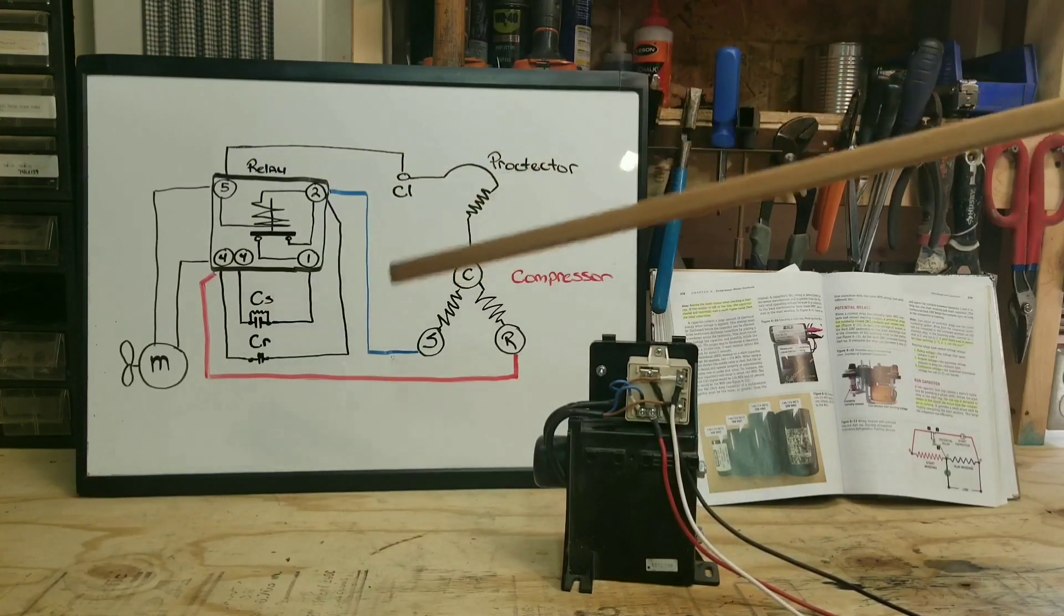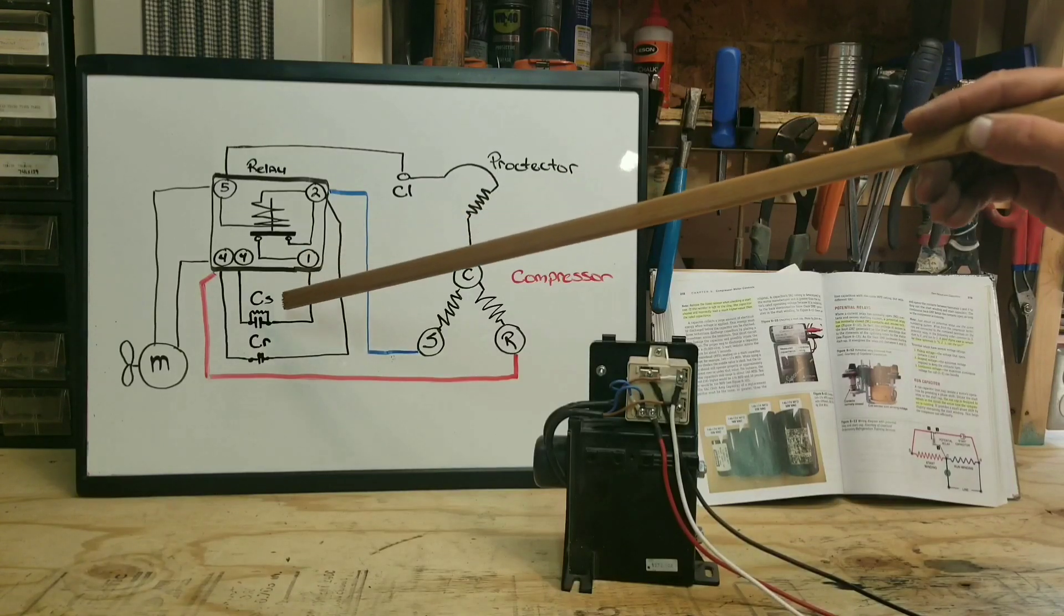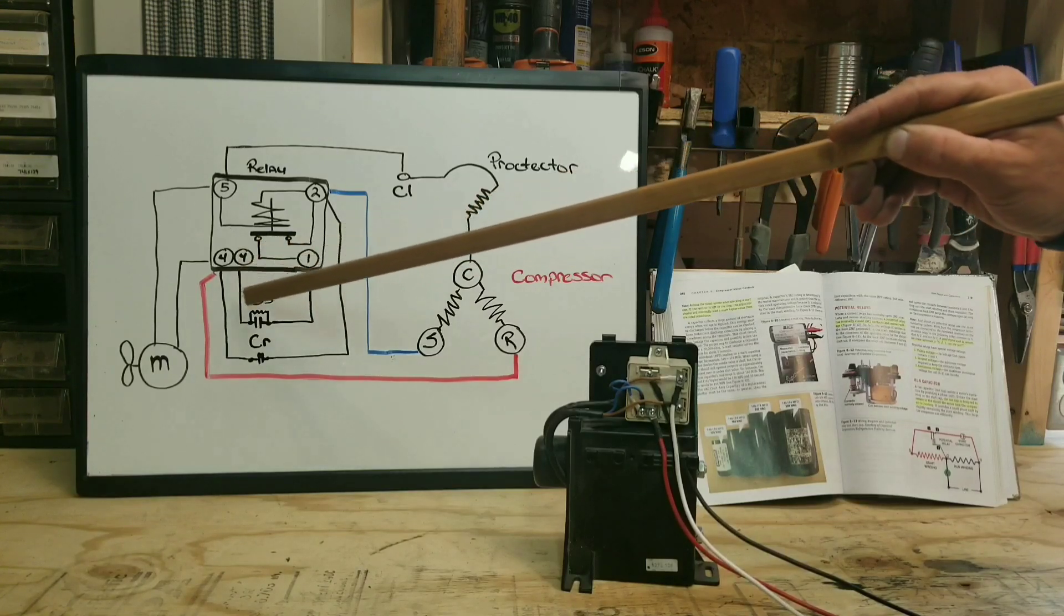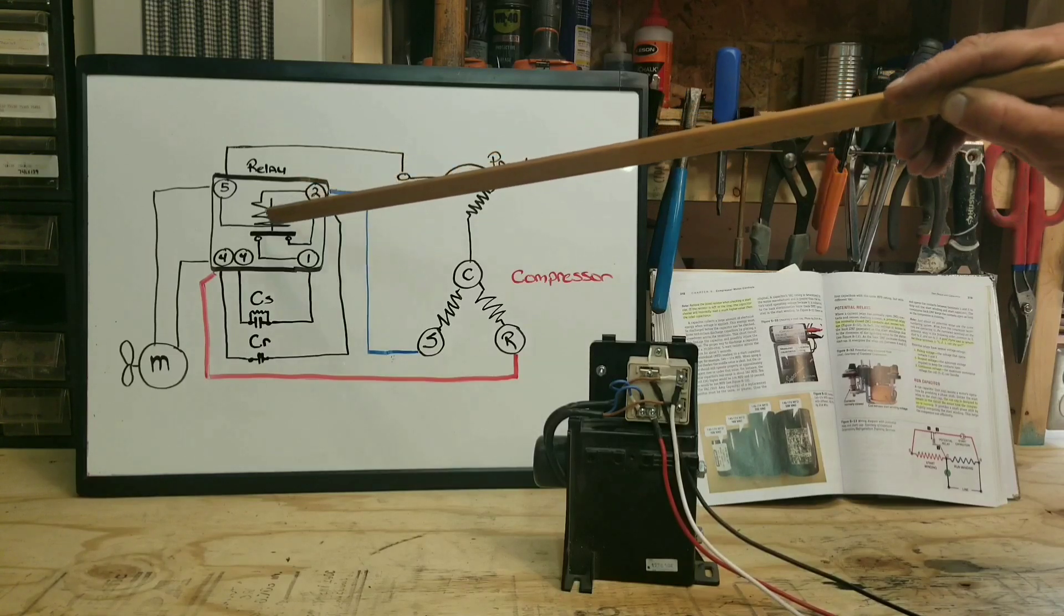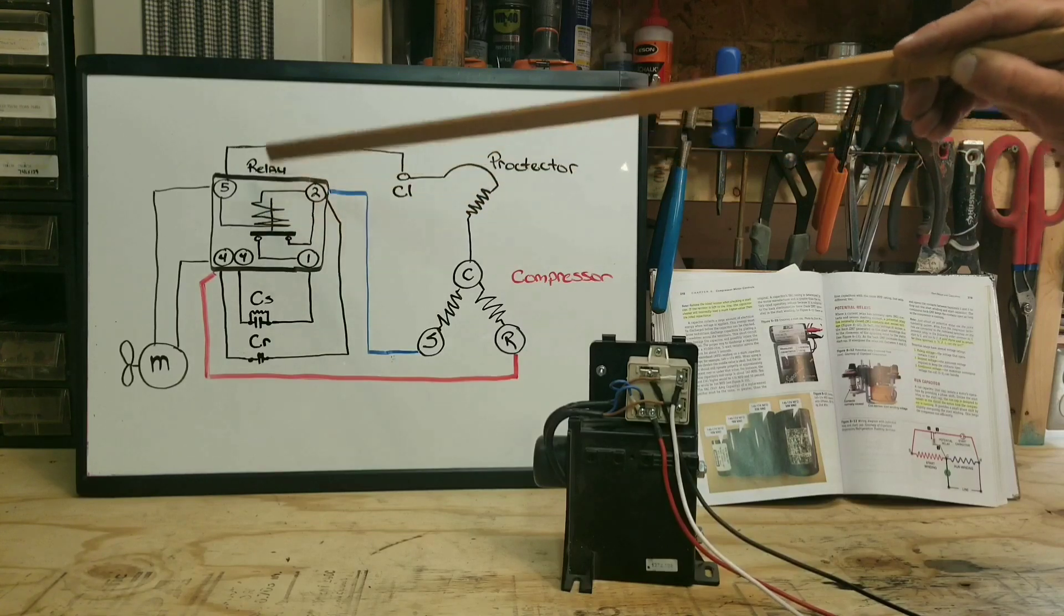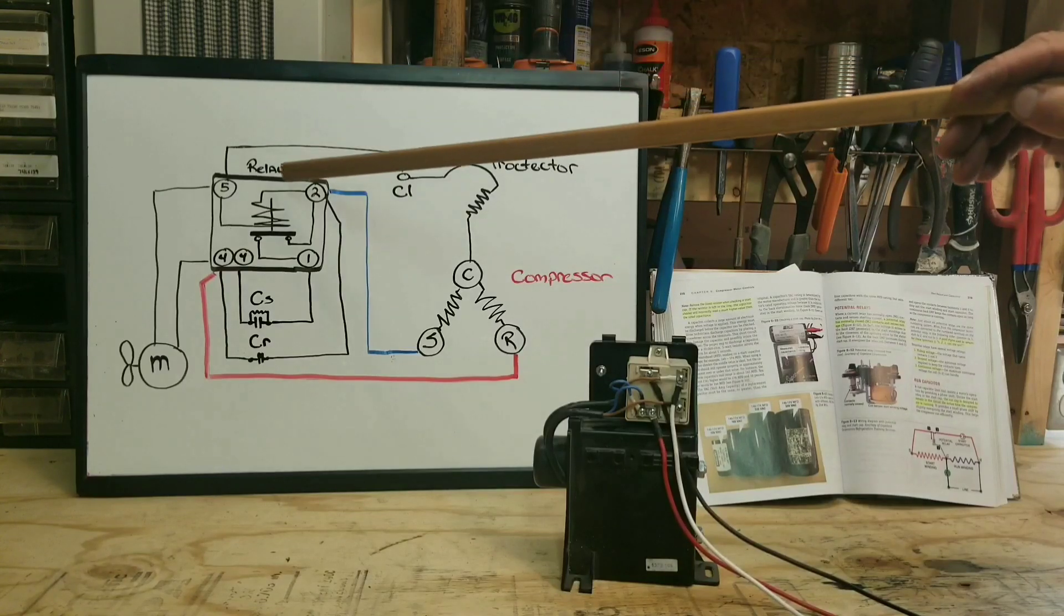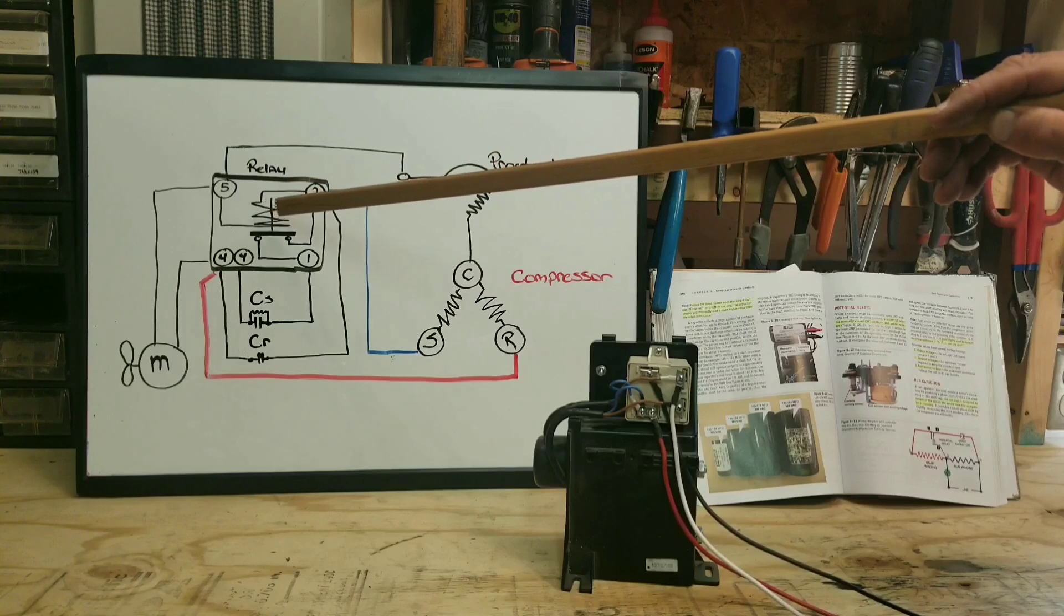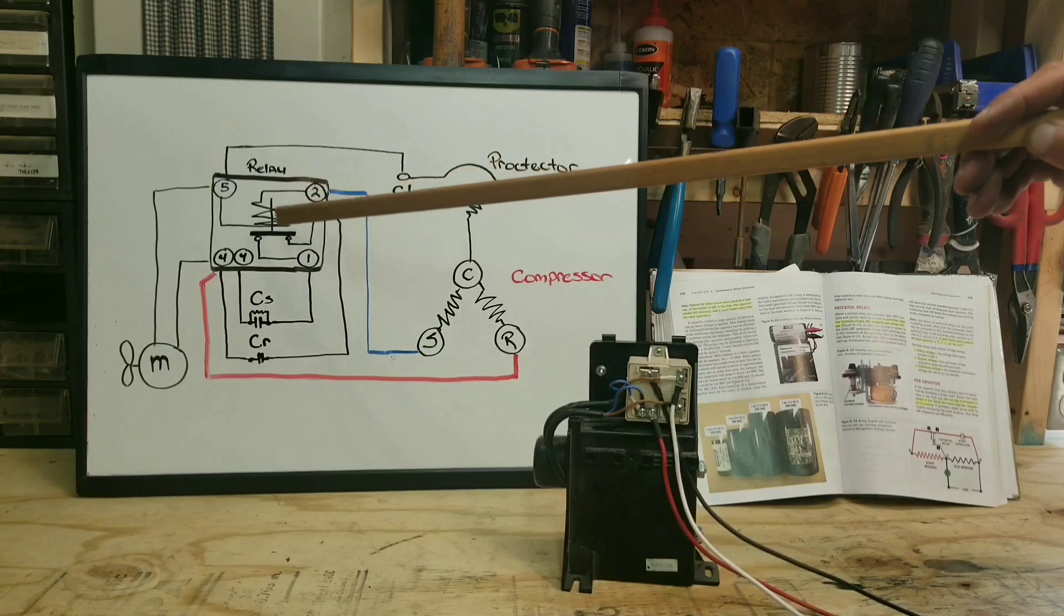Now after we get that compressor to turn over, we need to get that start capacitor out of the circuit. If you look at our start capacitor right here in our potential relay, in order to do that we need to have the terminals right here between one and two—we need to open those up. Now if you notice right here, forgive me I'm not an artist, but I drew it the best I could. So this squiggly line right here is actually the coil to this potential relay.